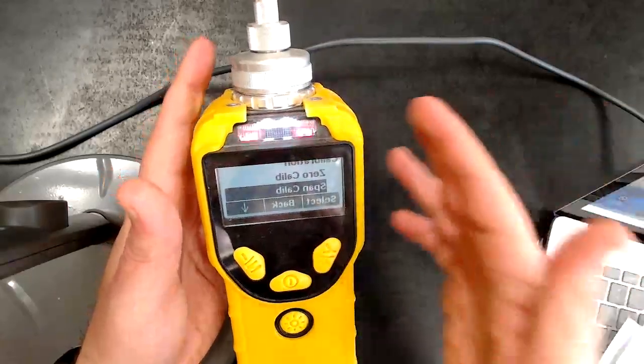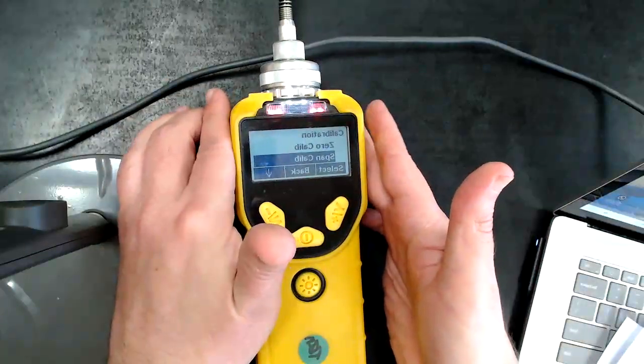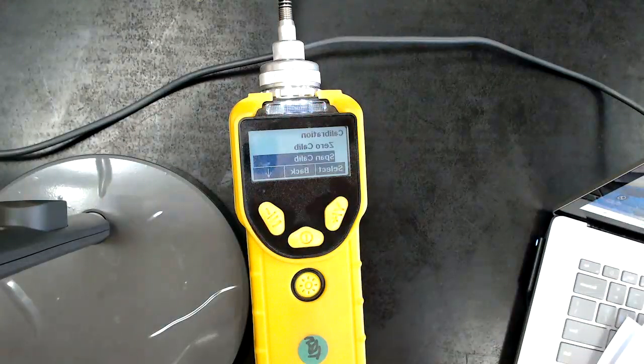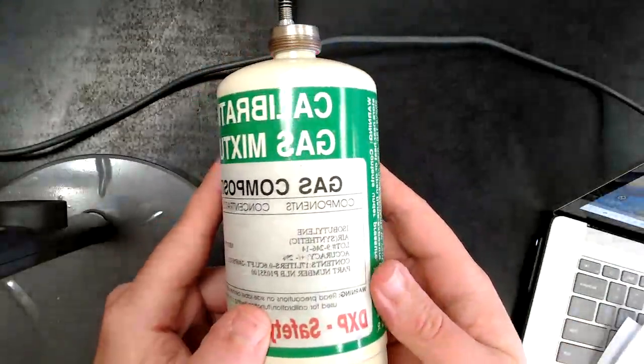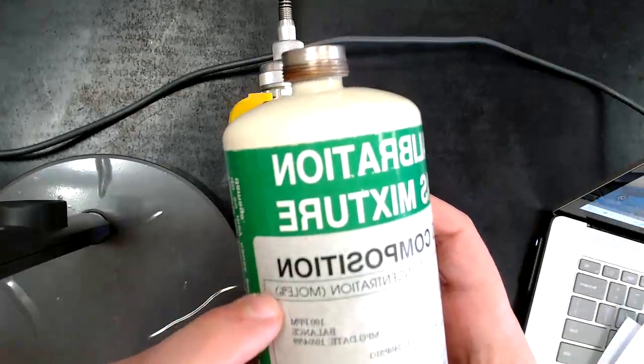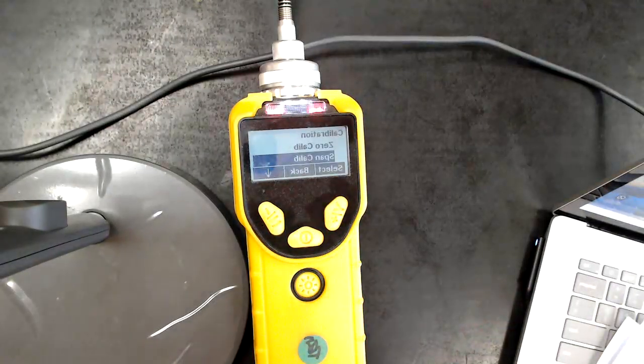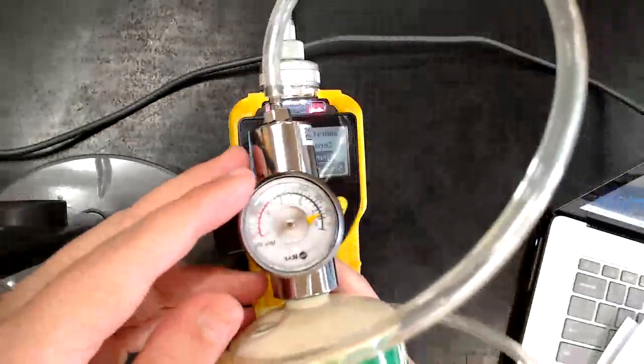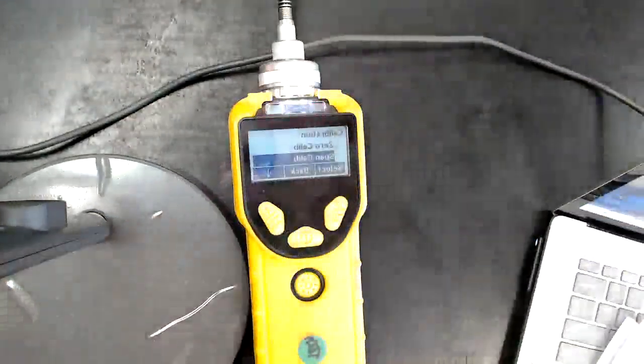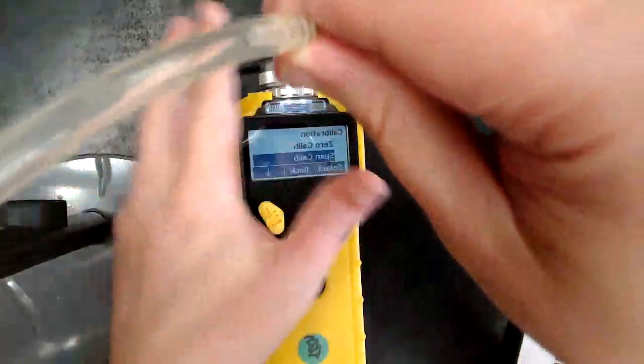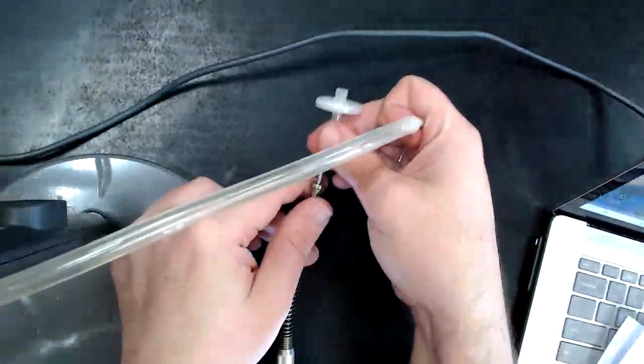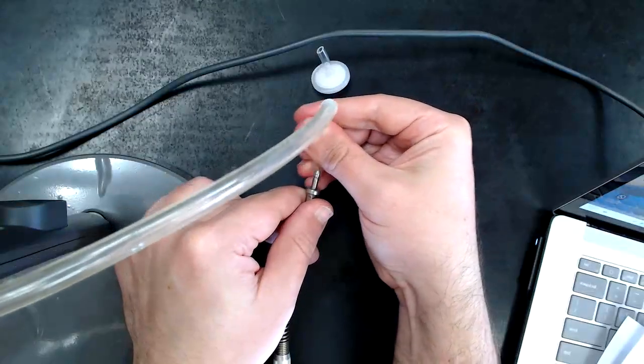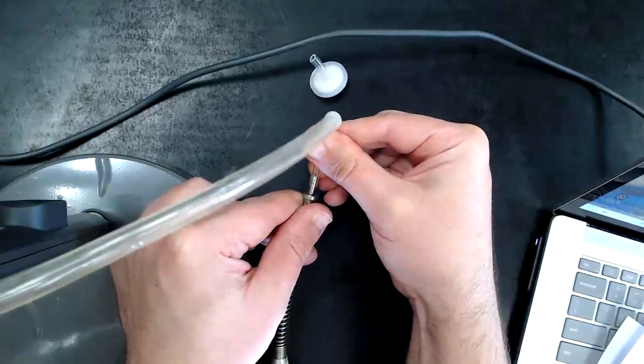Next is the span calibration. Depending on what you want to calibrate to, one of the most traditional gases is isobutylene, and we have 100 ppm. We'll put a regulator on here so we can connect it to the MiniRAE. We don't have that much, but it's definitely enough. We have the regulator on here. We're going to attach the tubing to the tip, and we're going to turn on that dial.